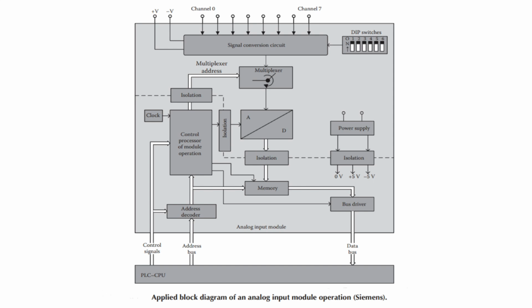The conversion time for each analog input is relatively short and typically ranges around 10 to 50 microseconds. Therefore, a module with multiple input channels can complete a full operational cycle in a fraction of a millisecond. This quick conversion time is significantly less than the typical scanning time of most programmable logic controller applications, and it ensures efficient and timely data processing.